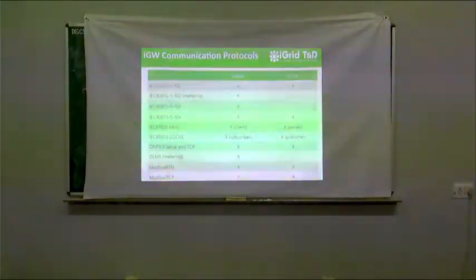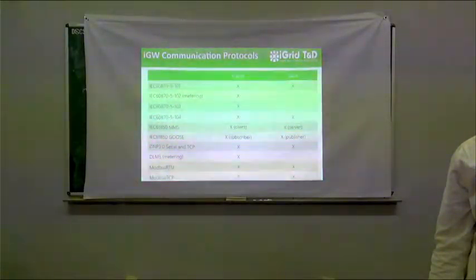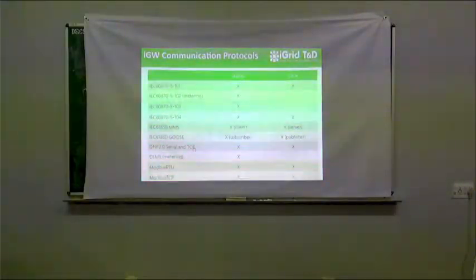So when I talk about different protocols, the product, the gateway, supports multiple protocols. That means as a master, from the downstream devices, I can read the data in IEC 101, 102, 103, 104, and it also supports IEC 61850. IEC 61850 is a suite of protocols that supports both MMS and GOOSE. In addition to that, it supports DNP3. DNP3 is a protocol which is basically used in the US and Canada, whereas in India we use the IEC 61850 protocol.